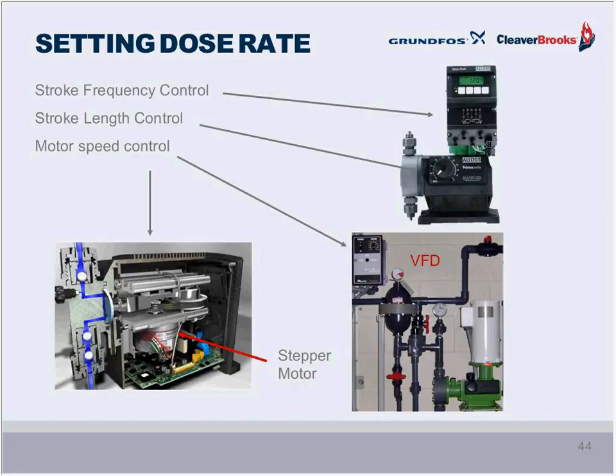So for motor-driven pumps, maximum stroke length can be described as 100%, and the maximum frequency of reciprocation can also be characterized as 100%. If you have 50% stroke length and 50% stroke frequency, then the total dose rate is figured by multiplying the two percentages. So for this example, 50% times 50% equals 25% of the maximum flow rate. These two factors, or any combination of the two, leave a seemingly endless variety of outputs. There are limitations, but that's getting so deep into the topic that we won't have time to cover it today. So another opportunity to learn awaits us.